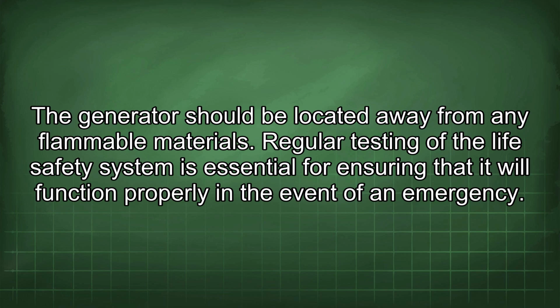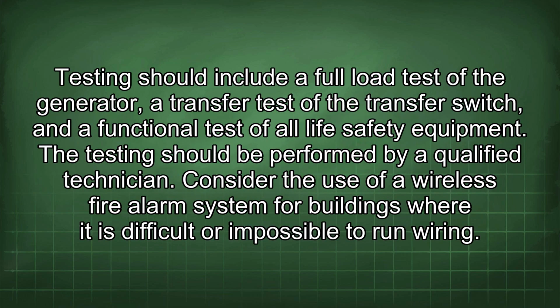Regular testing of the life safety system is essential for ensuring that it will function properly in the event of an emergency. Testing should include a full load test of the generator, a transfer test of the transfer switch, and a functional test of all life safety equipment. The testing should be performed by a qualified technician.